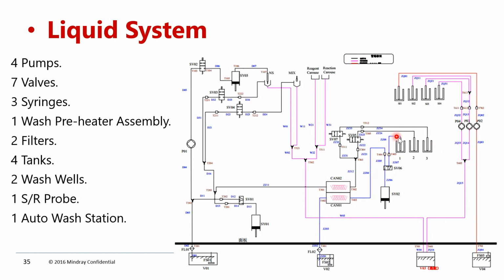So first it dispenses the detergent. Once a reaction is done, before sample dispensing, it will wash the cuvettes, right? So in the first step, this blue line is a detergent line. Syringe 2 will aspirate the detergent from the external tank through the preheater assembly, and it will dispense the detergent to cuvette number 1. Then this probe will aspirate the detergent from cuvette number 1 to a concentrated waste tank.